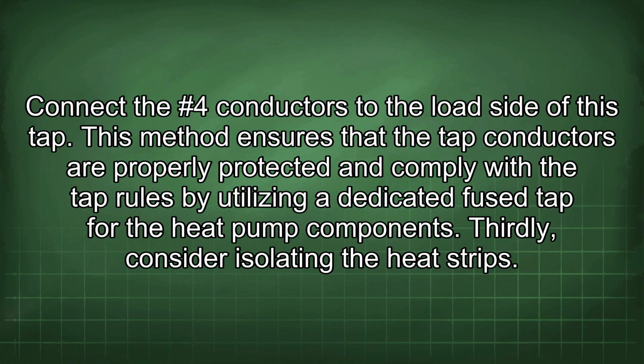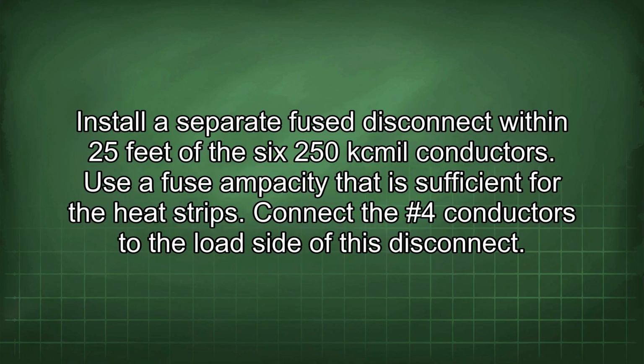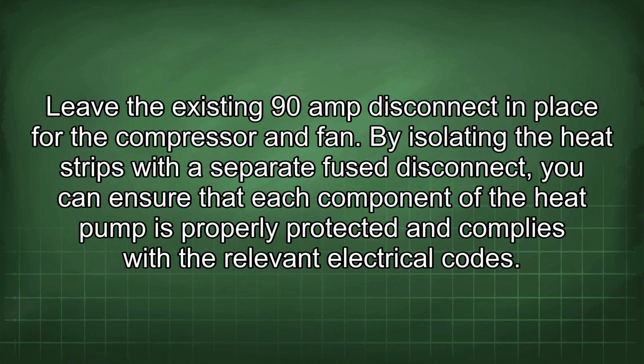Thirdly, consider isolating the heat strips. Install a separate fuse disconnect within 25 feet of the 6 250 kcmil conductors. Use a fuse ampacity that is sufficient for the heat strips. Connect the #4 conductors to the load side of this disconnect. Leave the existing 90-amp disconnect in place for the compressor and fan. By isolating the heat strips with a separate fuse disconnect, you can ensure that each component of the heat pump is properly protected and complies with the relevant electrical codes.